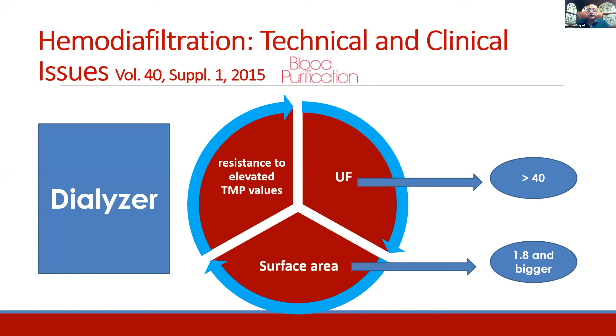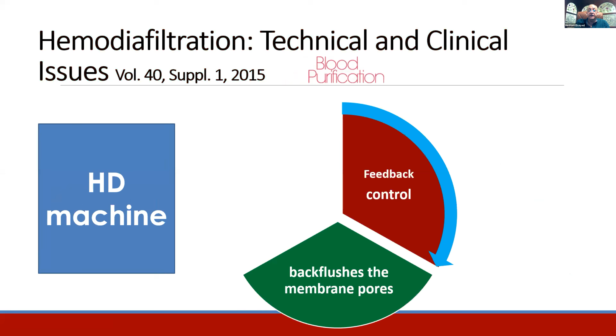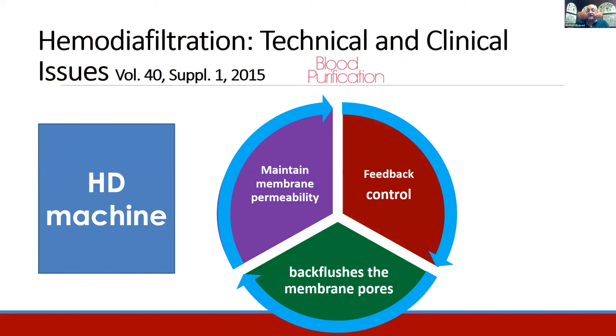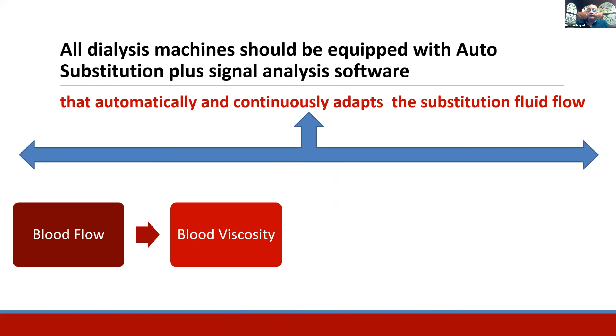For the surface area, I prefer 1.8 and bigger, resistant to elevated transmembrane pressure according to the membrane characteristics. The machine should have a feedback control and be able to back-flush the membrane pores, what is called back filtration on demand, to maintain membrane permeability. The factors are blood flow, blood viscosity, transmembrane pressure, and dialyzer characteristics. So one of the cornerstones is to select the dialyzer.